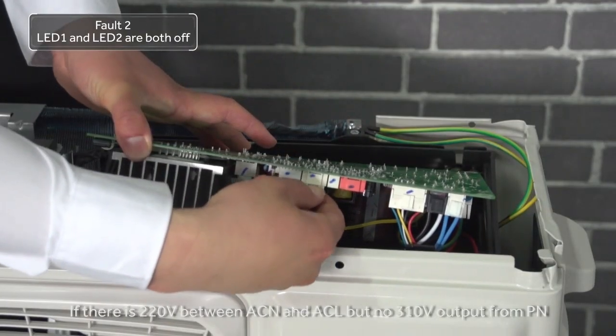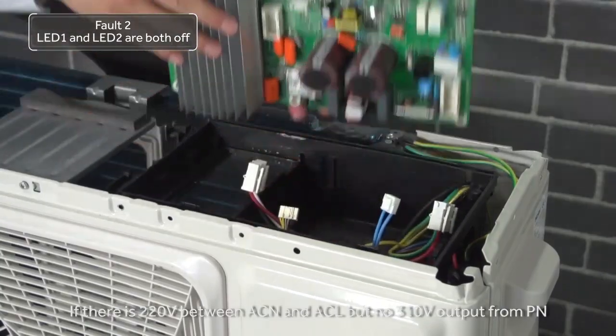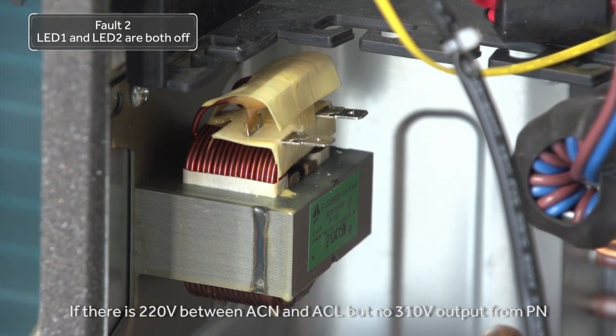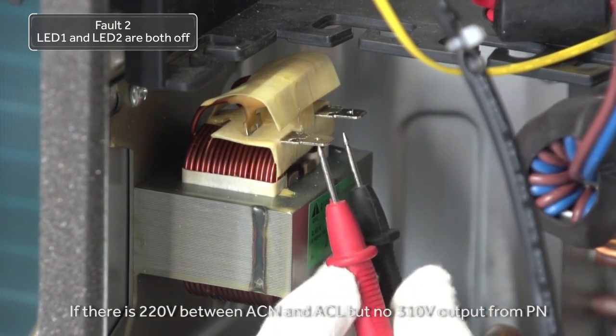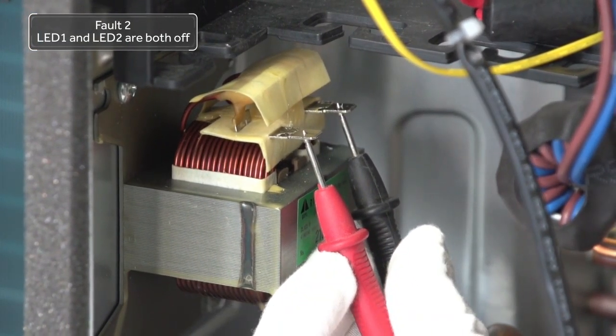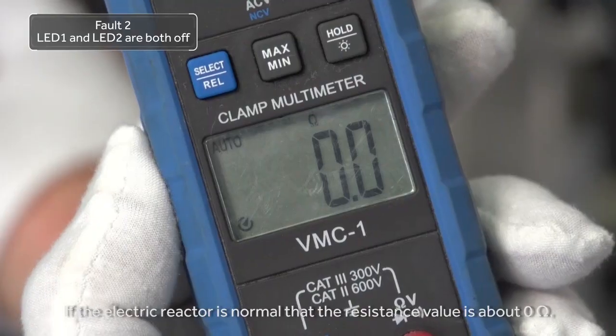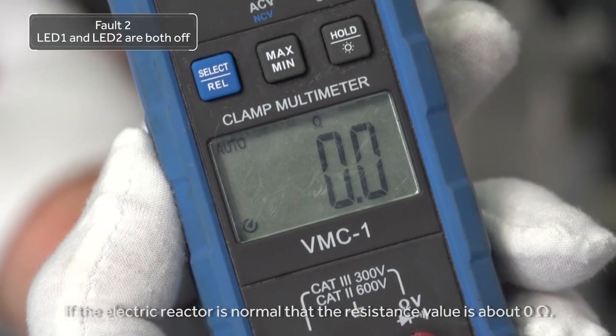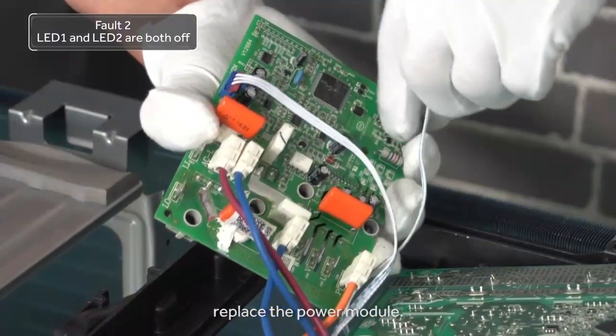If there is 220 volt between ACN and ACL, but no 310 volt output from PN, check the electric reactor. If the electric reactor is normal, that is, the resistance value is about 0 ohms, replace the power module.